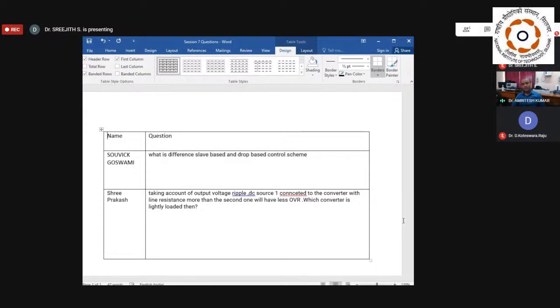That same concept is applied in the DC microgrid. Basically, many DC sources are connected to the DC microgrid, and based on the group, they are going to stabilize at one common DC bus voltage without any communication. So that is your droop-based control scheme. But you have seen that I showed you how this droop-based control has the effect of sharing equal current, but decreases the common DC link voltage. That can be easily sorted out by the secondary control.